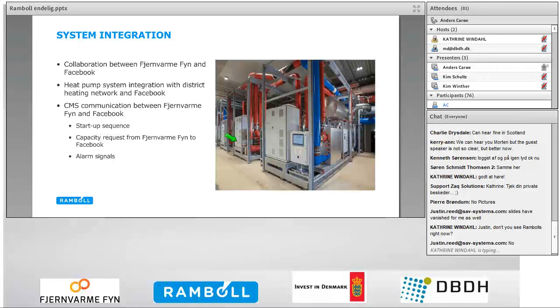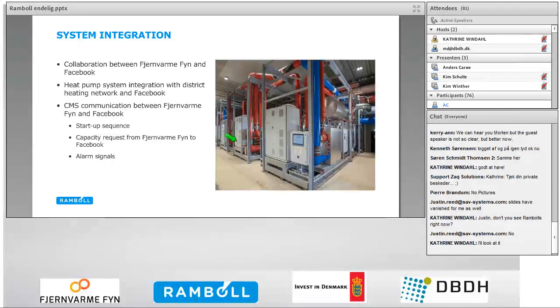When the plant is in operation, Fjernvarme Fyn will send a capacity request to Facebook, essentially asking to recover a certain amount of waste heat. And this signal exchange will also show how much heat is currently being recovered, and Facebook can use that to plan their operations. The two CMSs can also send alarm signals that will ensure that both Fjernvarme Fyn's and Facebook's systems can shut down safely if needed.